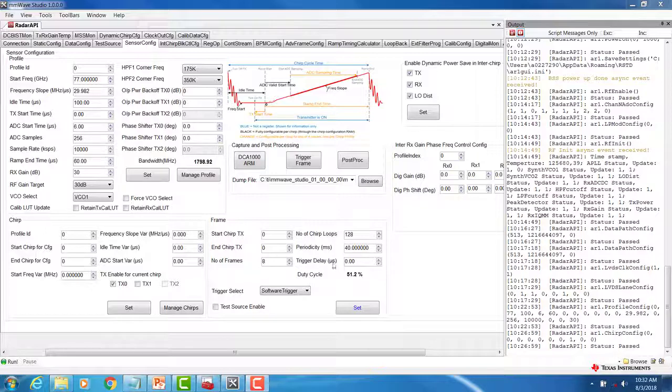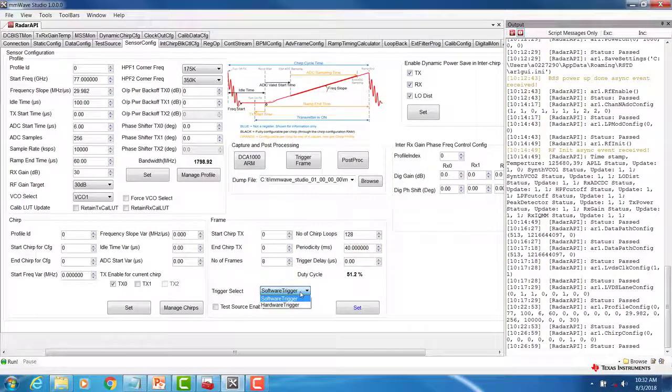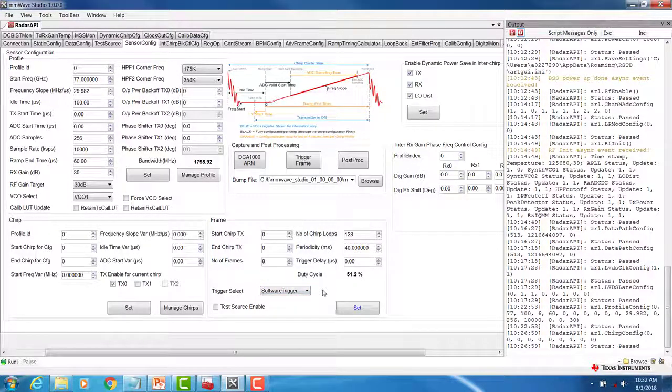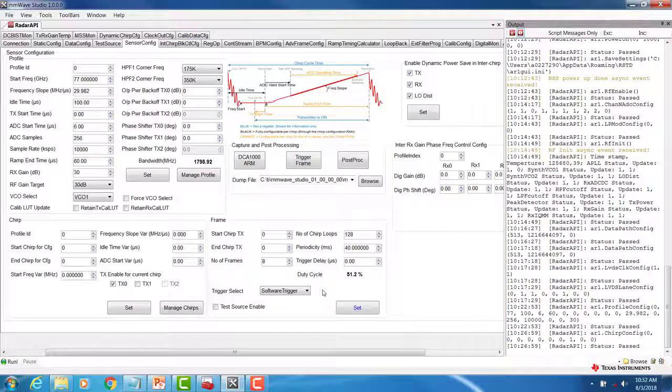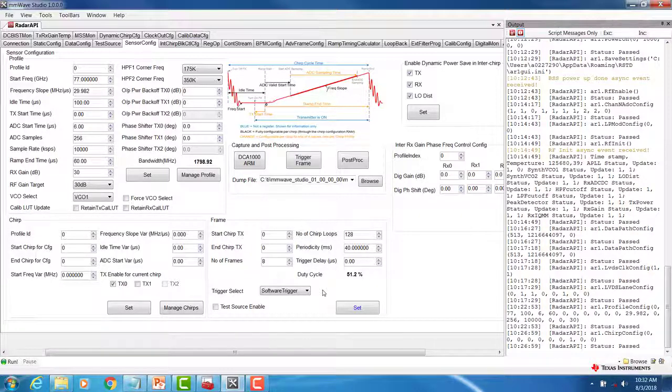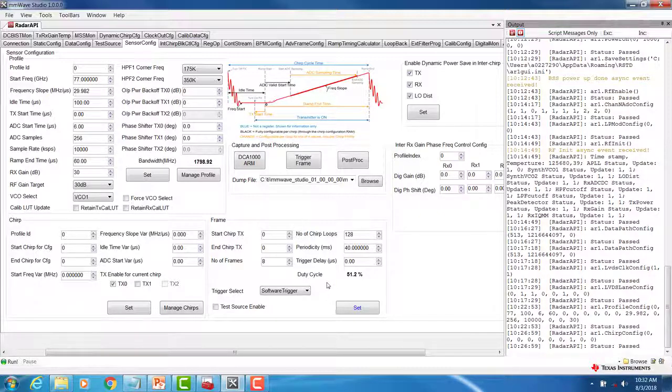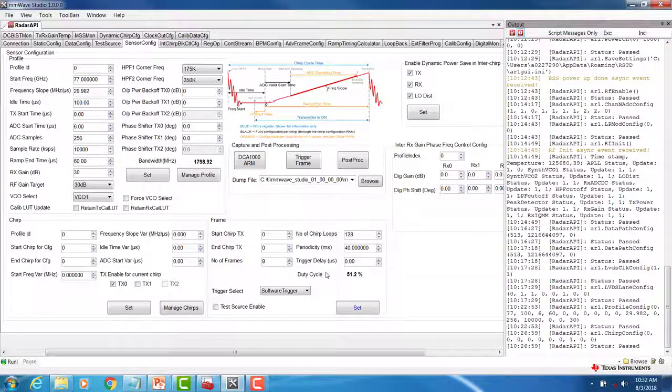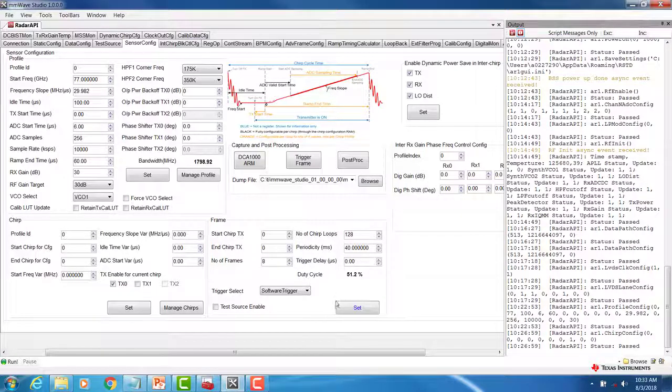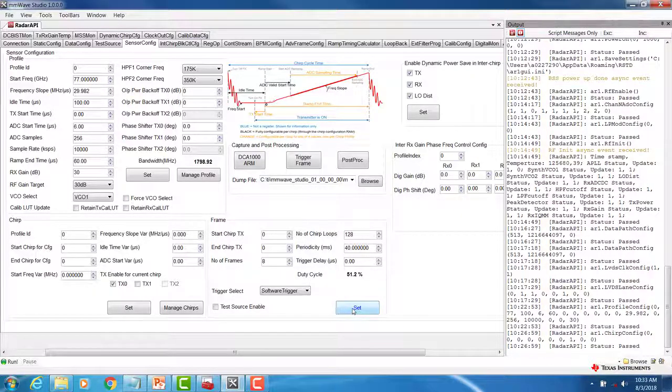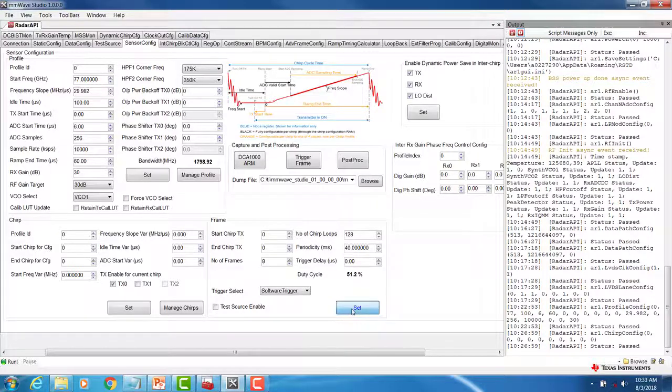Additionally, we can add a trigger delay and select the trigger for a software trigger or hardware trigger. With a hardware trigger, the frame will be triggered by an external source on the digital sync pin, which is typically used in cascade applications. In our case, we will leave the default values and click SET when you are done configuring your frame.